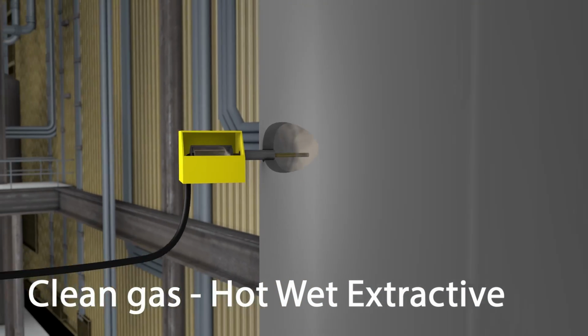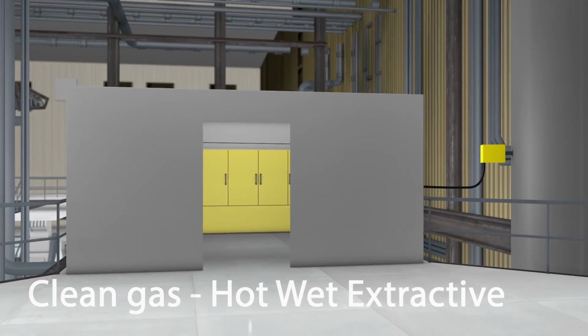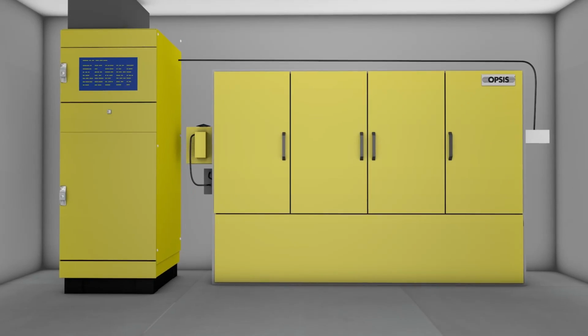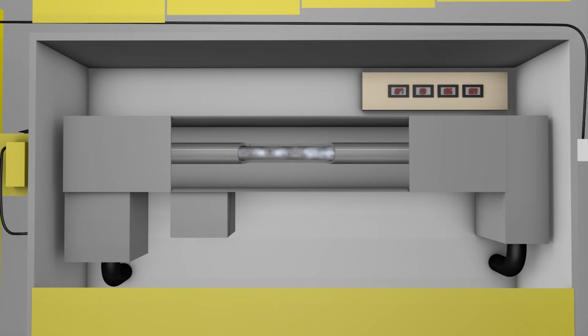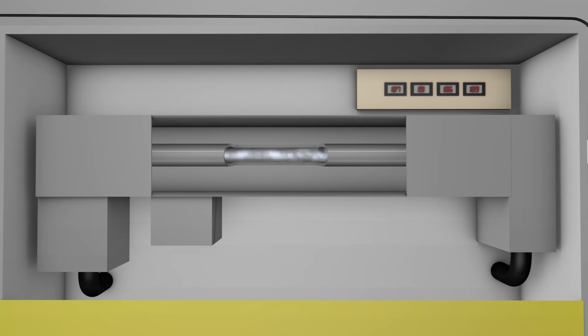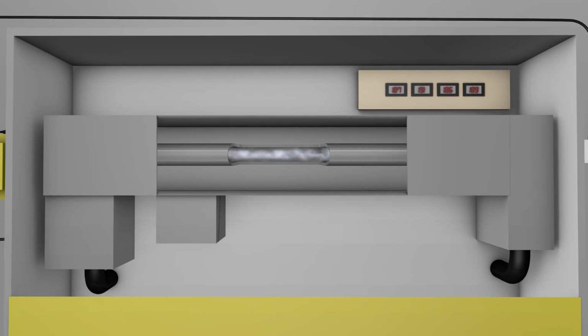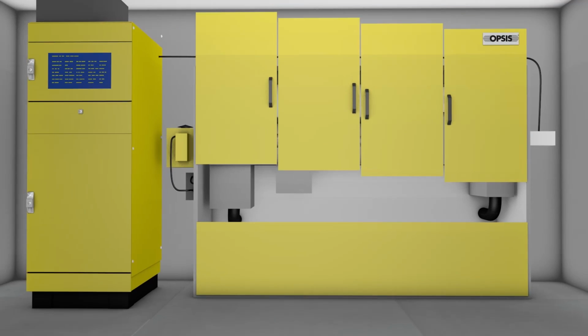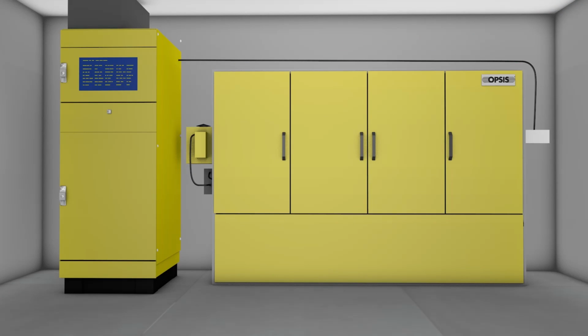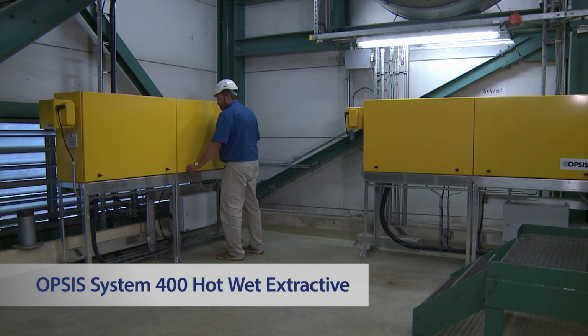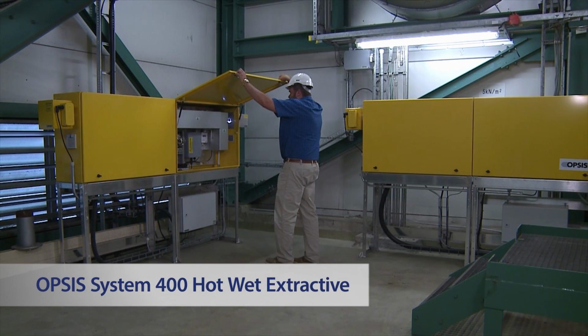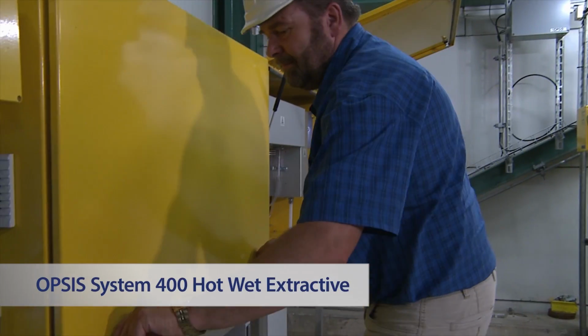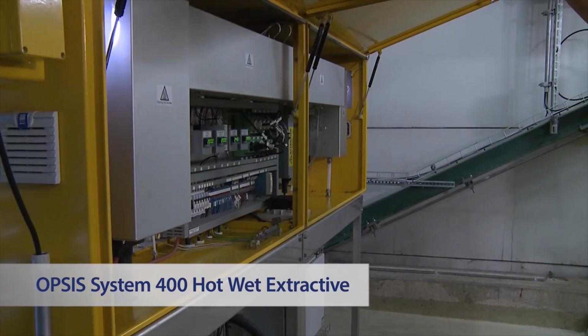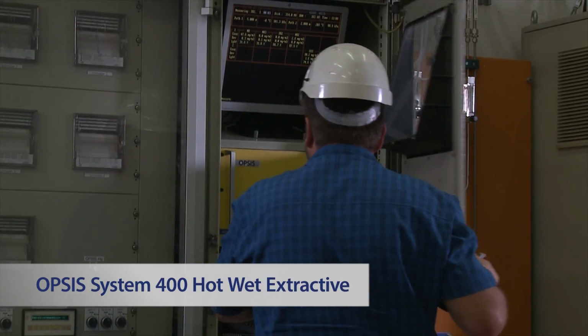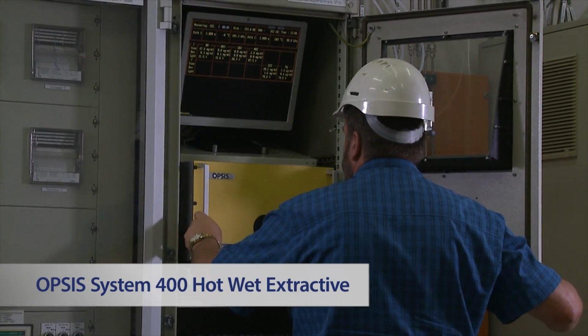The gas is sucked out and let through a filter which extracts the particles from the gas. The flow rate is low, only a few liters per minute. The gas is further led via a heated sample line to the measuring cell, which here is positioned next to the analyzer cabinet. The measuring cell can also be placed in a separate room, as in this facility. Here, the measurement cells are situated in one part of the plant, while the analyzer is installed in another part.